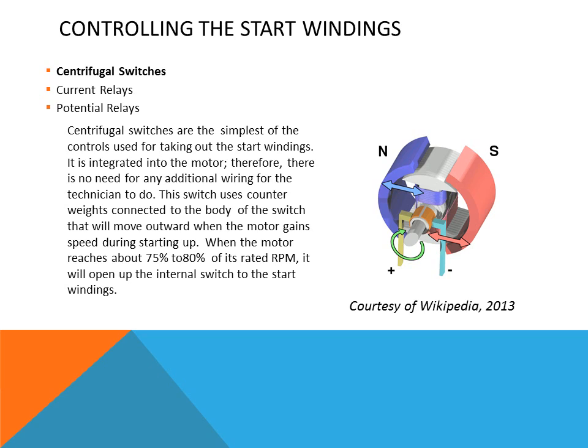The centrifugal switch is the simplest type — it uses a mechanical action with counterweights that use centrifugal force to move linkages inside the motor, opening up the start windings when the motor reaches full speed. As soon as the motor slows down or stops, the switch will close again.